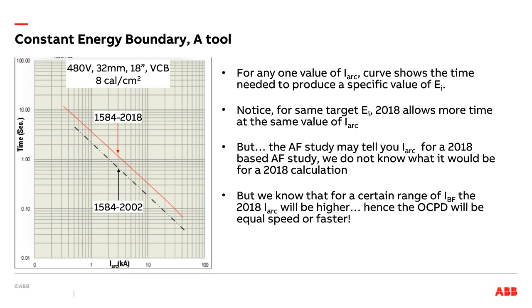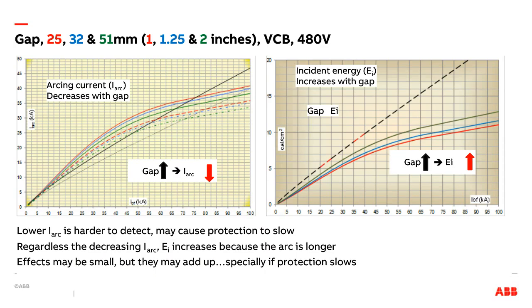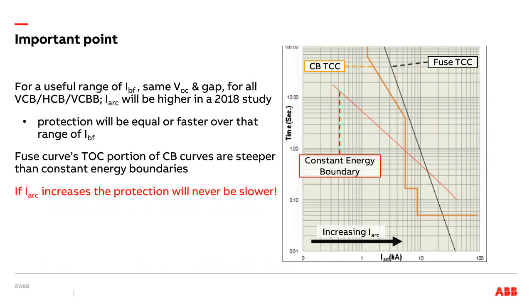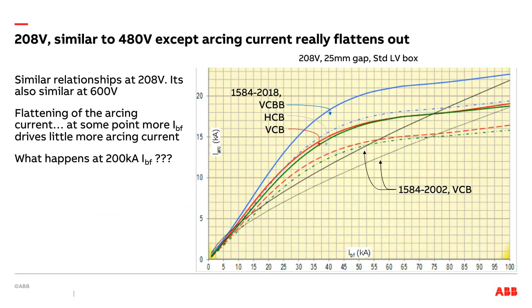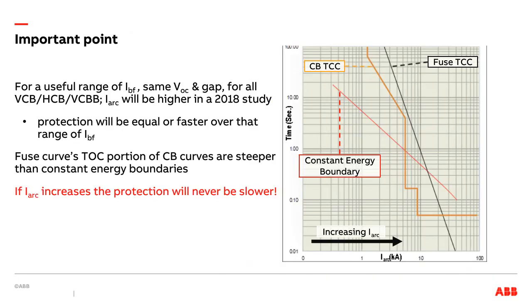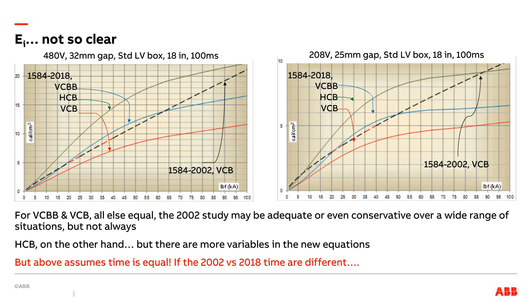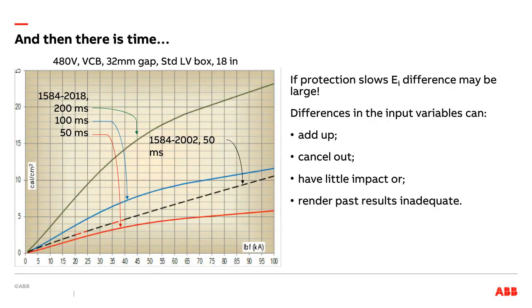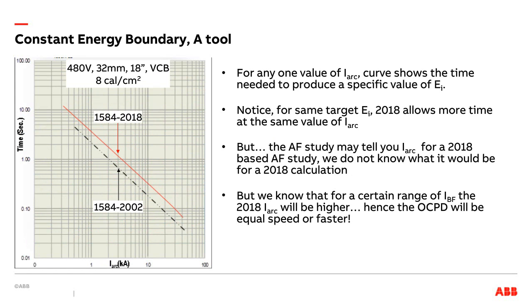And if you look at the previous chart, 2 previous charts, 3 previous charts, 4 previous charts, that makes sense because the arcing currents are different. Actually, not so much because of that, but because the energy, difference levels are different. Notice that the red line is below the black line here. In this chart, that is shown the other way around. You have more flexibility in time because the energy per unit time is lower. This becomes a useful analytical tool when you do not have an exact value of arcing current or an exact value of bolted fault current.